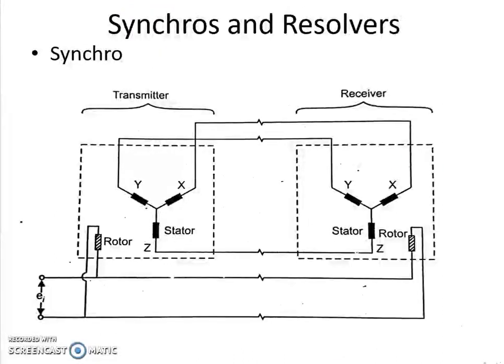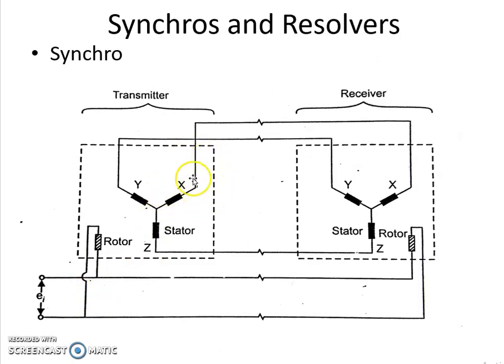Now let us discuss about synchros and resolvers. These are a class of AC electromechanical variable coupling transformer devices, basically used for angular data transmission. The basic structure of a synchro consists of a wound rotor and a wound stator, mutually coupled to each other. The rotor is wound with a single-phase concentrated winding, and the stator is wound with three-phase distributed windings connected in a star configuration.